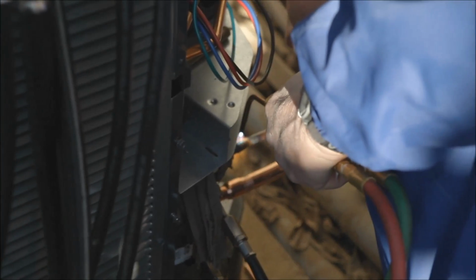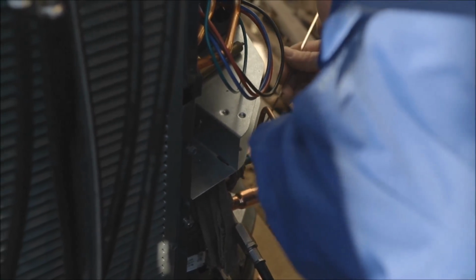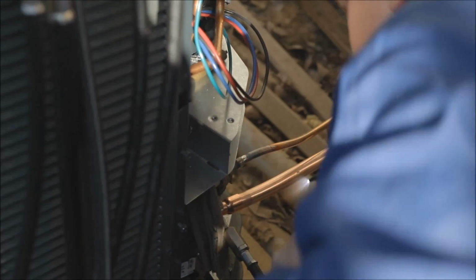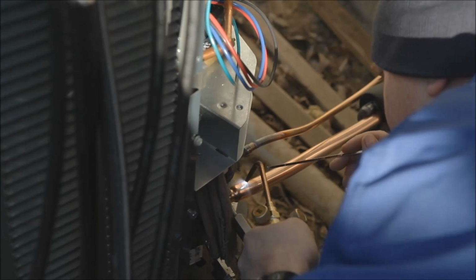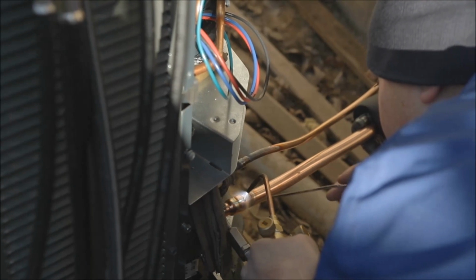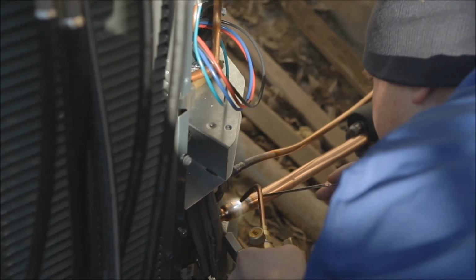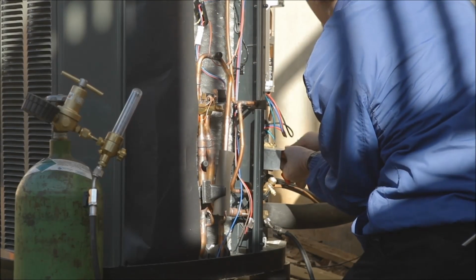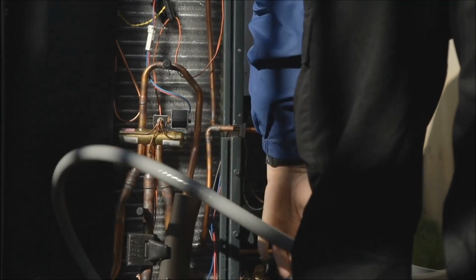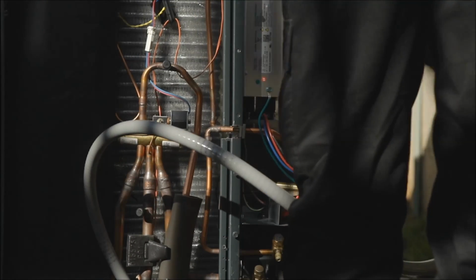You can see the technician brazing the refrigerant lines to the unit's service valves. It is important to remember to remove the valve cores. Wrapping a wet cloth around the valve body reduces the possibility of heat damaging the valve. The technician installs electrical supply to the equipment from the disconnect on the house. The electrical supply should be checked for proper voltage, wire, and breaker size.